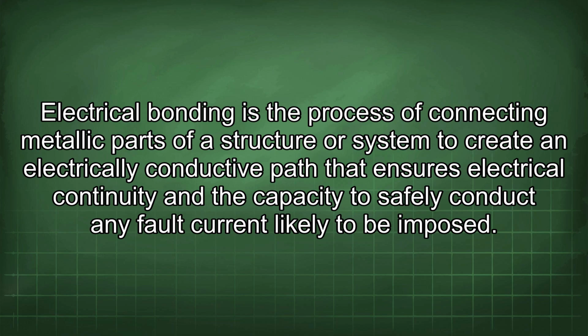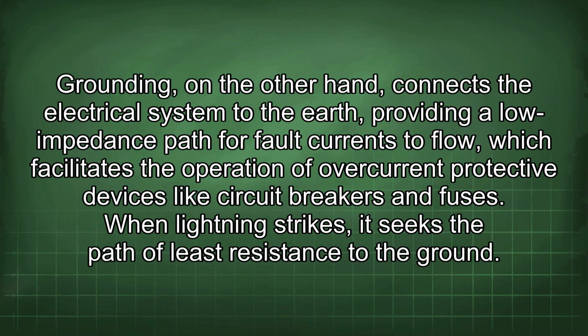Electrical bonding is the process of connecting metallic parts of a structure or system to create an electrically conductive path that ensures electrical continuity and the capacity to safely conduct any fault current likely to be imposed. Grounding, on the other hand, connects the electrical system to the earth, providing a low impedance path for fault currents to flow, which facilitates the operation of overcurrent protective devices like circuit breakers and fuses.